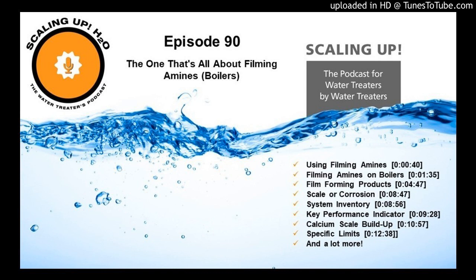So I can measure a polymer loading until the cows come home. And so, okay, what does that tell me? It tells me a polymer level. It doesn't necessarily tell me how well something is doing. What I really care about is corrosion rate. The same thing is true for filming amines. Okay? So that's one piece. Let's look at our ultimate key performance indicator. Let's look at how we are marking success. Are we marking it by saying, okay, I can do 10 different tests and then I can show that I've done 10 different tests? Or are we looking at it based on what really matters? In my mind, that's corrosion rate.